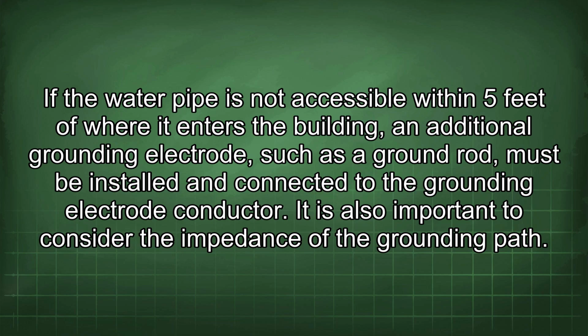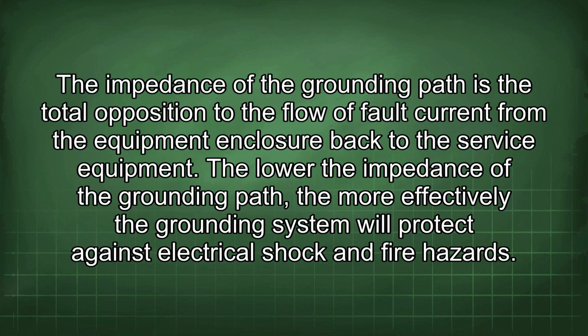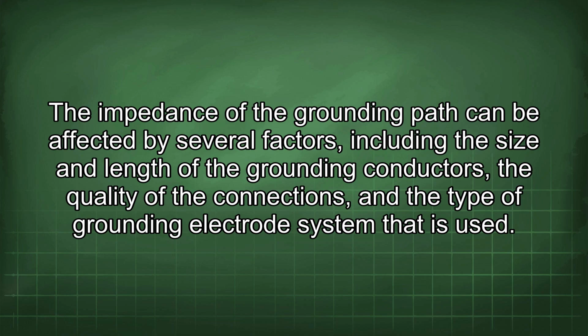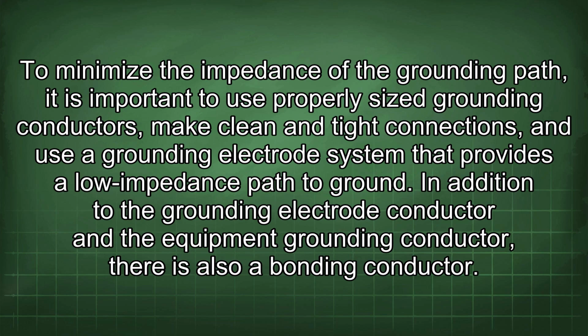It is also important to consider the impedance of the grounding path. The impedance of the grounding path is the total opposition to the flow of fault current from the equipment enclosure back to the service equipment. The lower the impedance of the grounding path, the more effectively the grounding system will protect against electrical shock and fire hazards. The impedance of the grounding path can be affected by several factors, including the size and length of the grounding conductors, the quality of the connections, and the type of grounding electrode system that is used. To minimize the impedance of the grounding path, it is important to use properly sized grounding conductors, make clean and tight connections, and use a grounding electrode system that provides a low impedance path to ground.